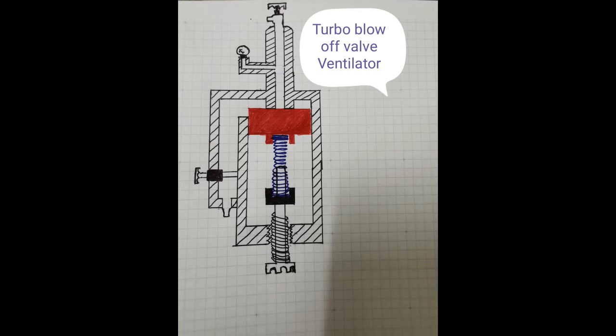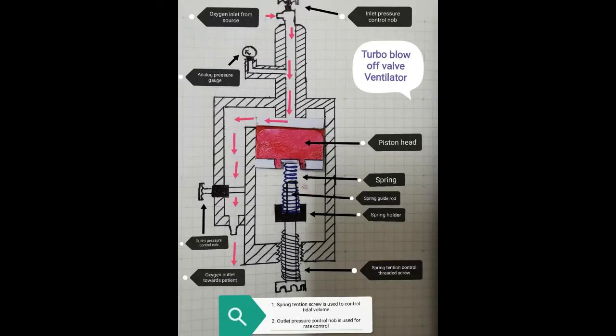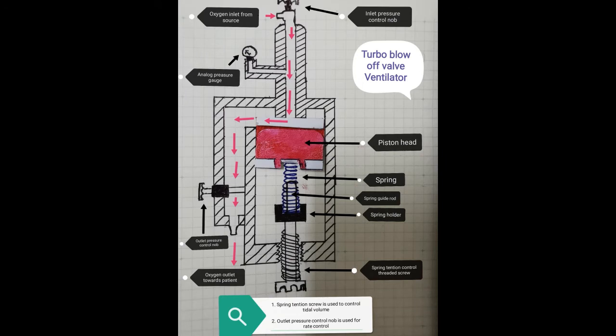Let me give you a brief on the components in this cross section that you see, which are listed from top to bottom. Oxygen inlet from source, inlet pressure control knob, analog pressure gauge, piston, spring guide rod, which is to guide the spring movement, spring holder, which is attached to the bottom of the screw, and ideally it should be mounted on top of a bearing or a shaft or a roller, whatever you might call it. This way, turning the screw will not add additional rotation torque to the holder or spring. Outlet pressure control knob or screw, oxygen outlet port, and finally you have spring tension control threaded screw.